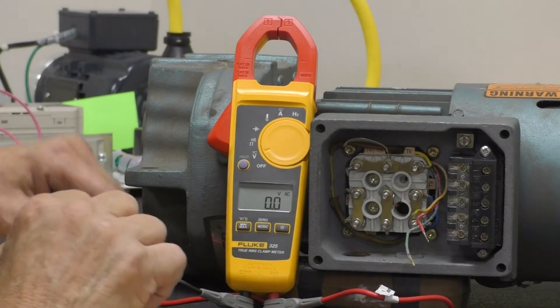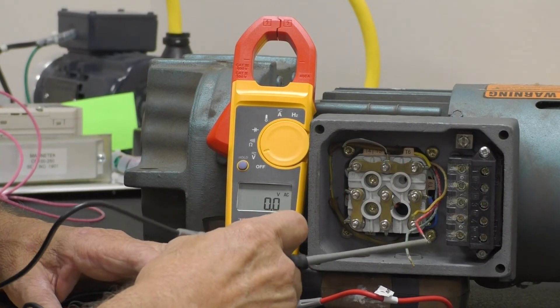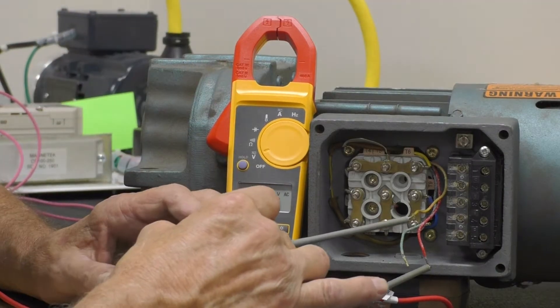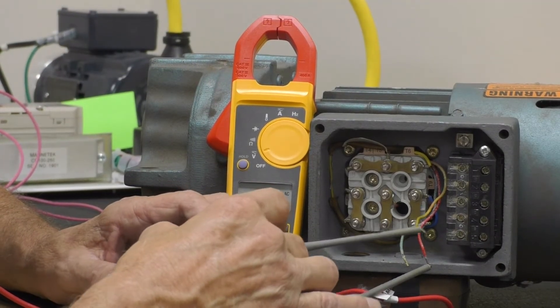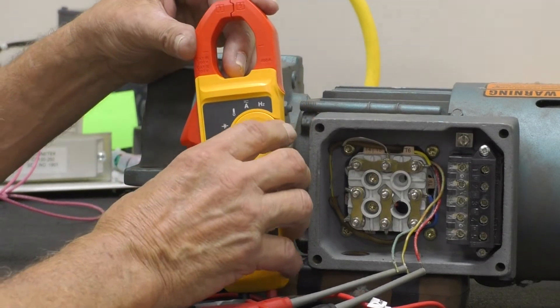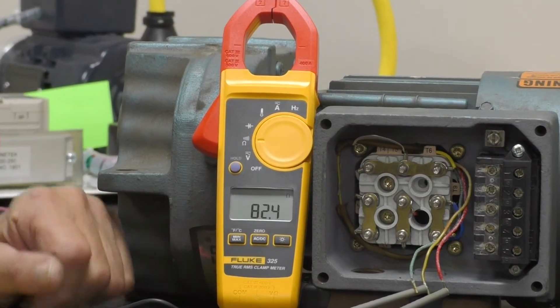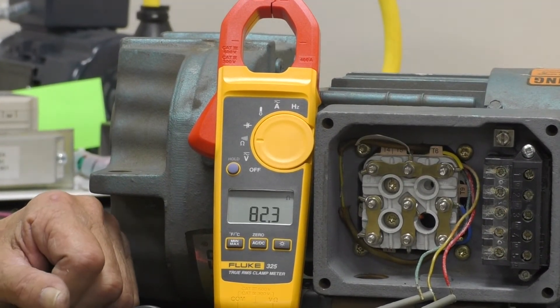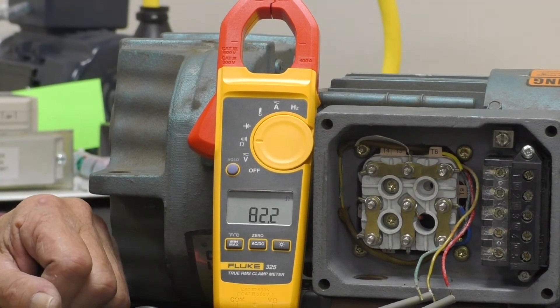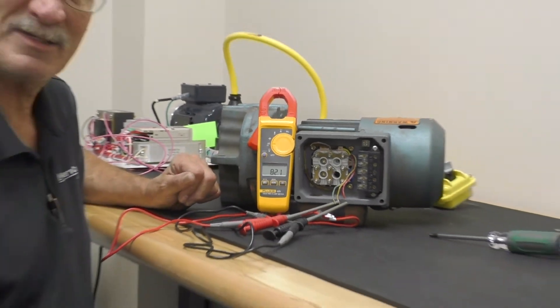Now I am going to put my black probe on my red wire and my red probe on the white wire, changing my settings from volts AC to resistance on the omega side. I should be reading 171 ohms. I am reading right now 82 ohms, which tells me the brake coil is bad.